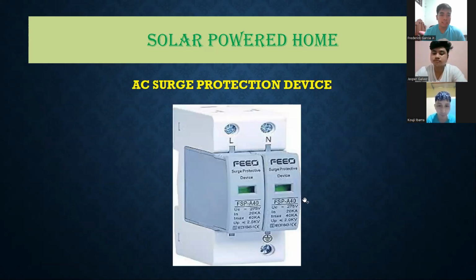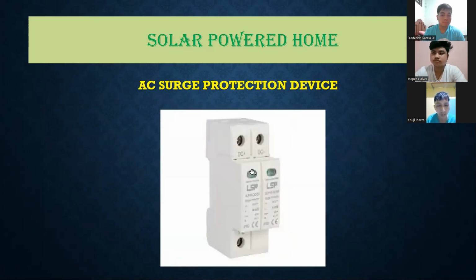We also have an AC surge protection device, much akin to the DC surge protection device. We have the gang one. The live wire goes here and the neutral wire goes here. And of course, we need an earth line in the event of transients, so the transient voltage has somewhere to go. We have another example of the AC surge protection device. And once again, 3 terminals: DC positive, negative, and ground.